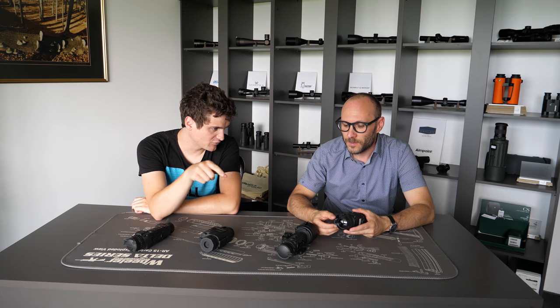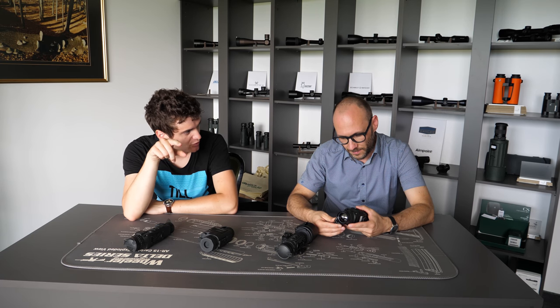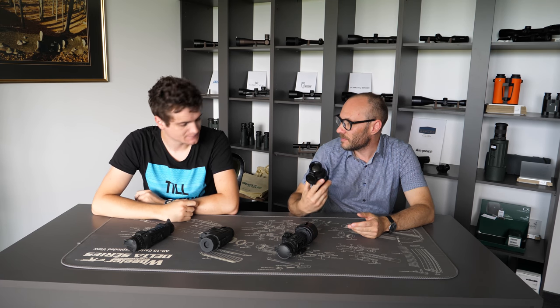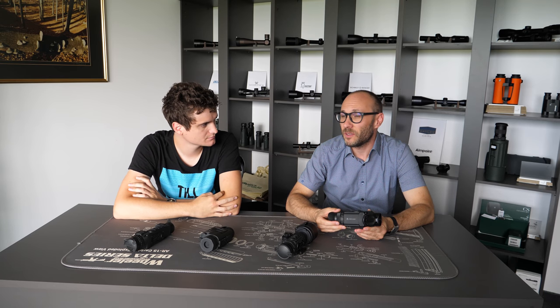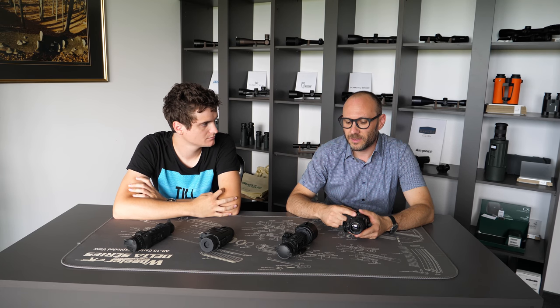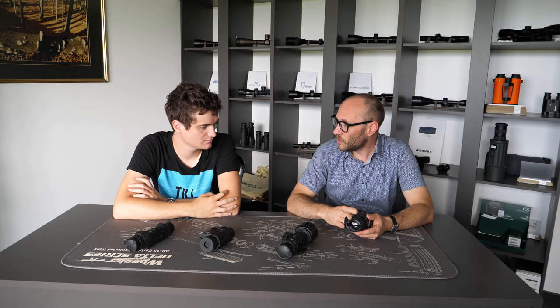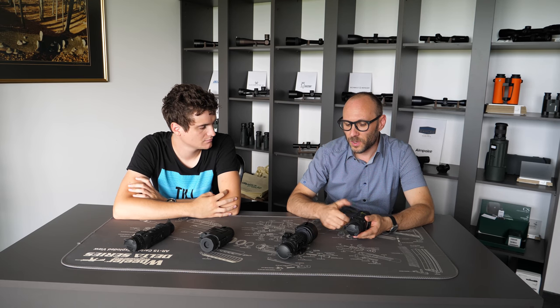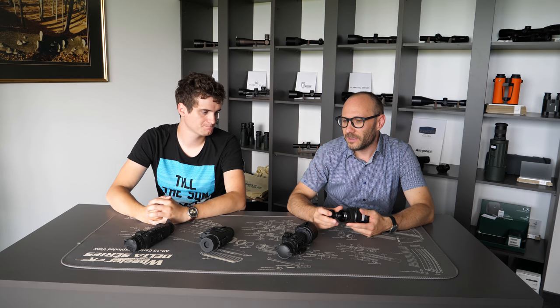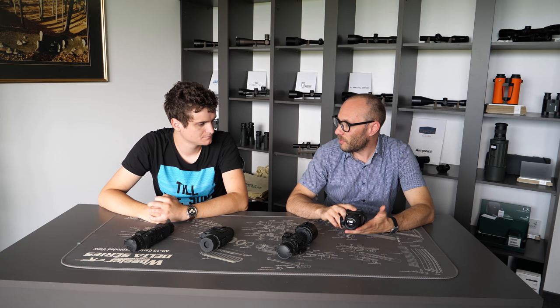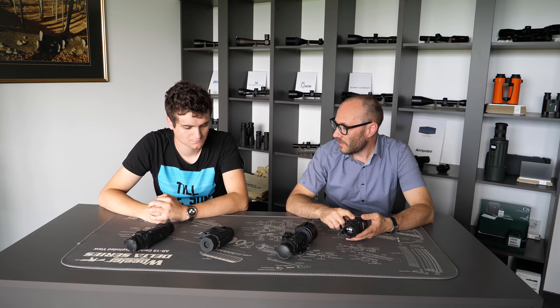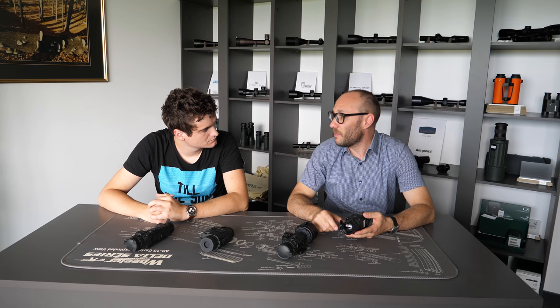But before you do that, you have to set it in the settings, right? Yeah. The semi-automatic, because all of these devices come with the default setting of automatic calibration. So you have to set semi-automatic, which means it gets calibrated when you power it on. Then when you're using it, no calibration happens if you're not pushing the button. And then you have the third version, which is manual.